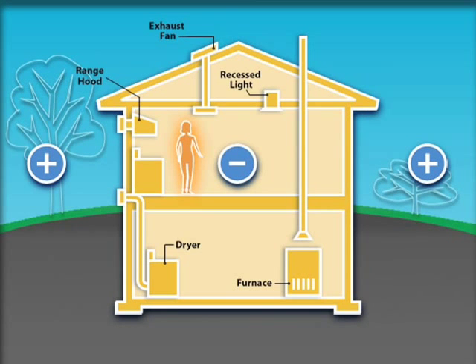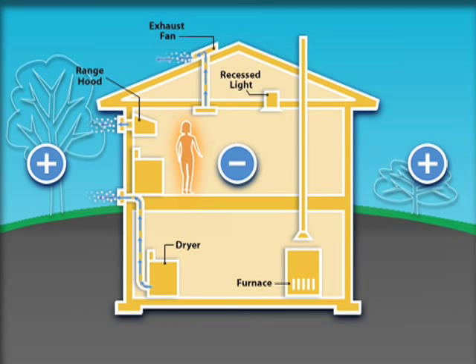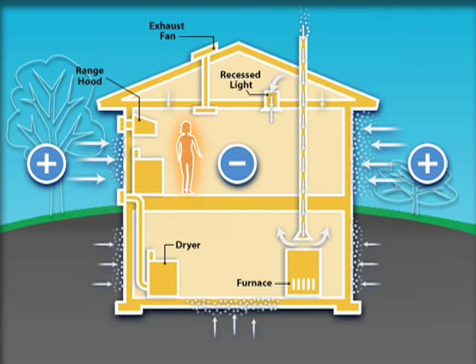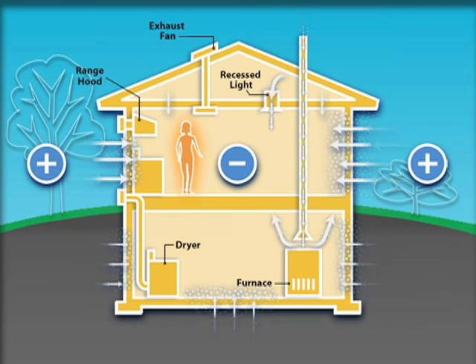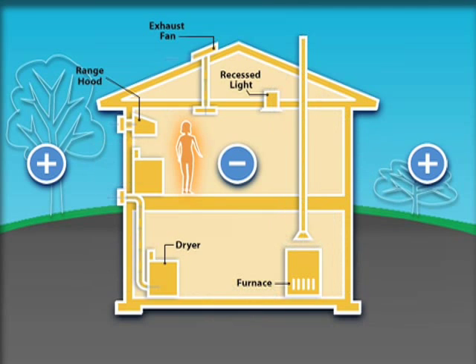Another source of air pressure can come from our mechanical systems. Each time we operate a fan, whether the range hood, central vac, or clothes dryer, we create a difference in pressure that can draw air and water vapor into the home. This replacement air enters the home through the path of least resistance, which often times is the flue or chimney. This can compromise indoor air quality.